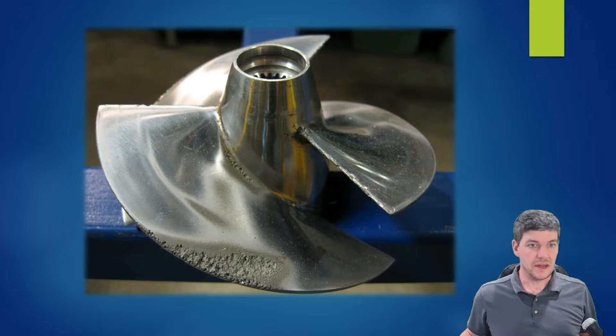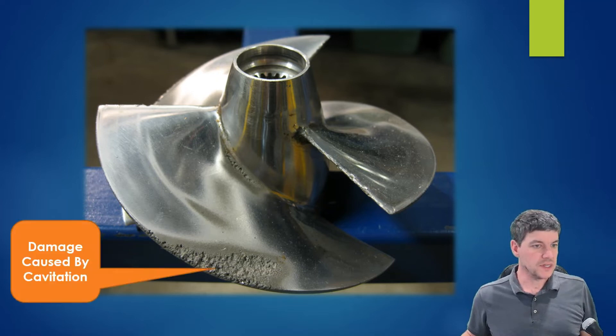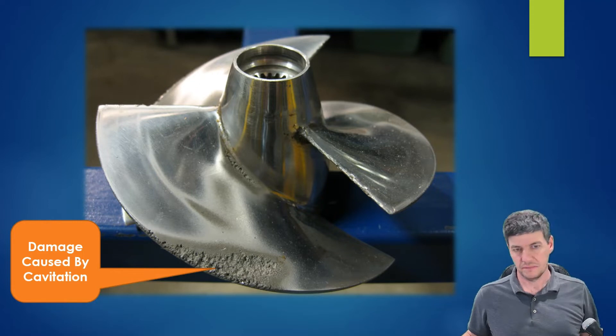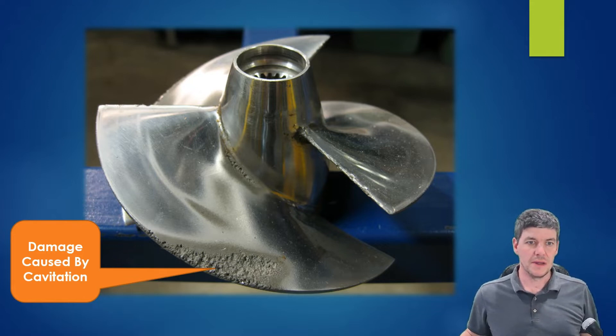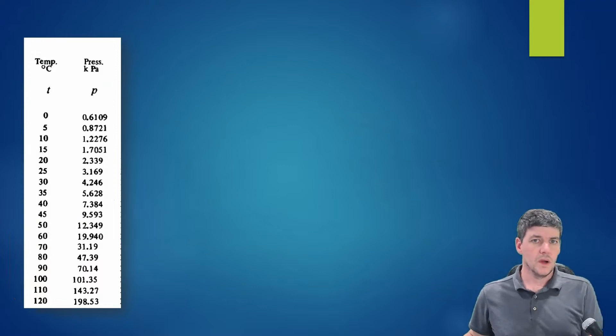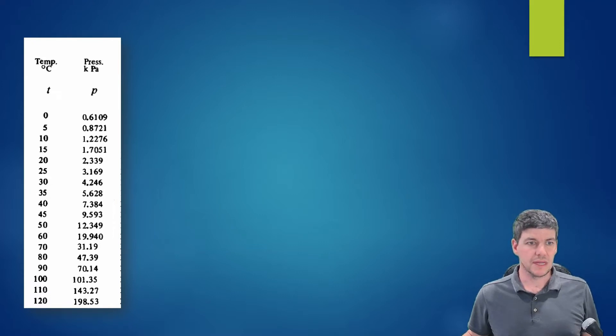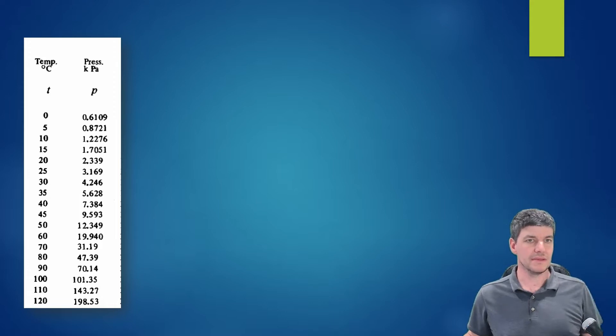Here we've got a pump impeller showing what looks like cavitation damage — essentially little holes smashed into the surface. Cavitation is a problem that occurs if our pumping system is not performing correctly. To understand how cavitation develops, we need to know the relationship between temperature and pressure when it comes to phase changes in a liquid. Here's a table of water showing temperature versus pressure at saturation conditions.